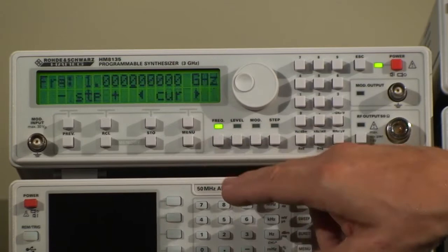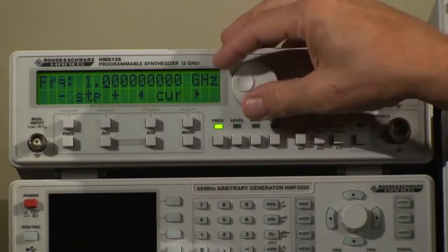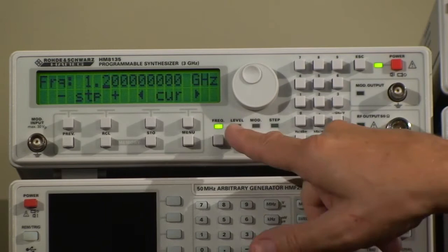Very straightforward. Press the frequency button, and now you have cursors moving back and forth here. If I want to set the frequency 1.2 gigahertz, that's what I'm doing.